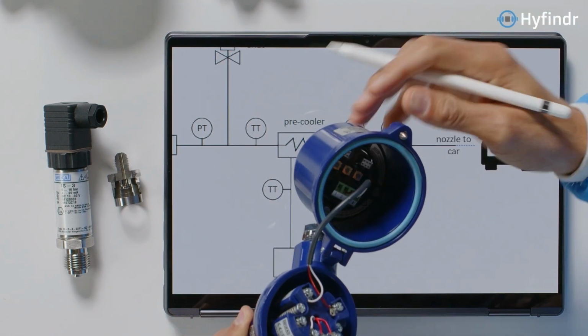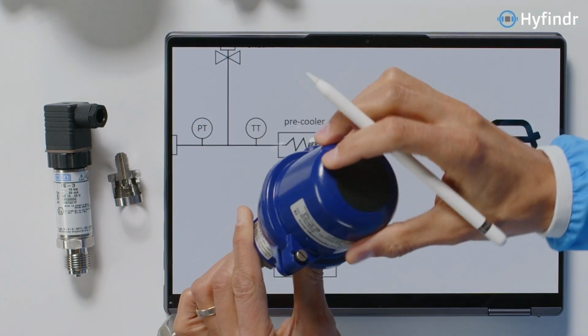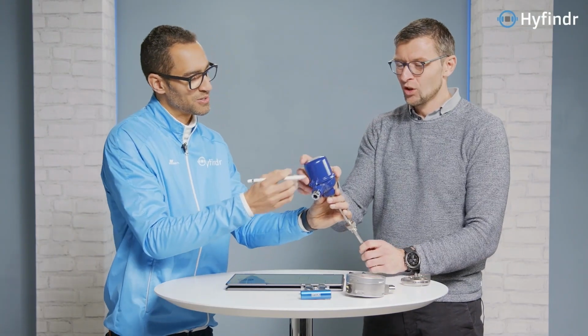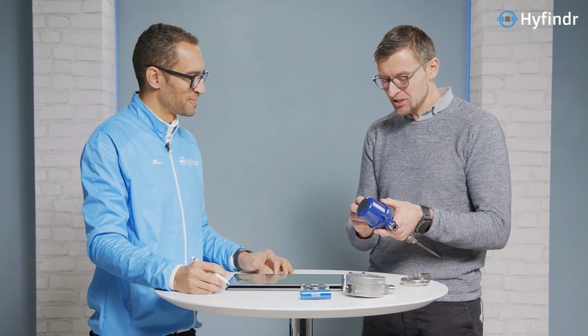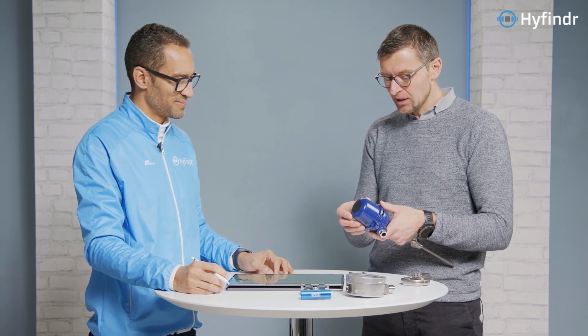Okay, and this goes out there, and you have this - this is shock protection? Or why is it such a big, colorful cover? It's actually a mechanical protection on the one hand. It's also a safety issue, because all of this instrumentation has to be explosion proof - we're talking about ATEX or IECEx requirements or local certifications. This adds additional safety so that nobody is able to get down to the transmitter, and it also protects from the environment.